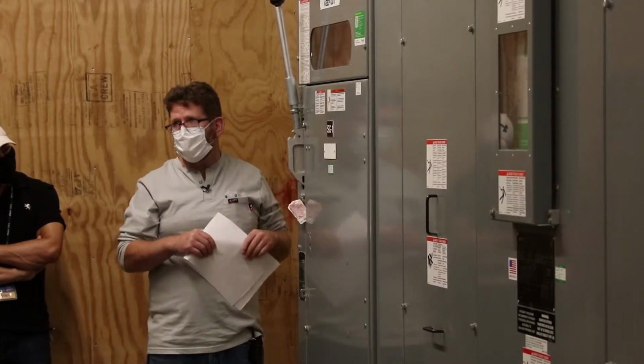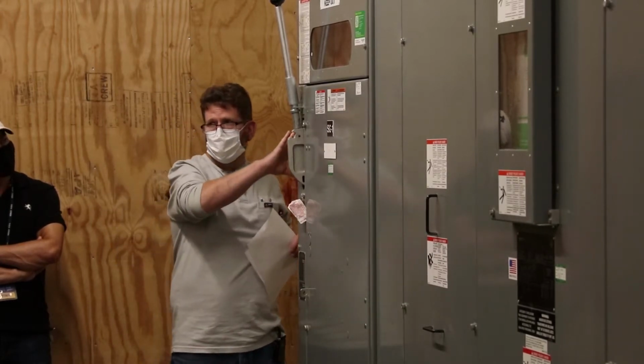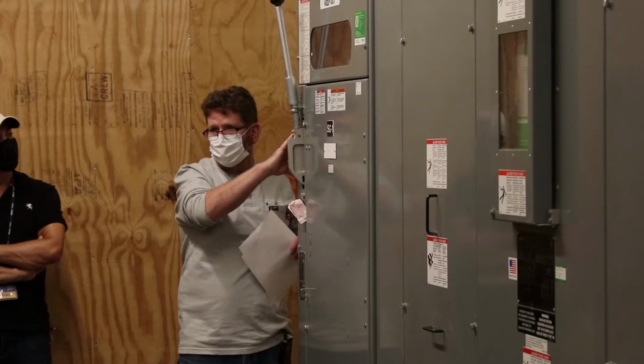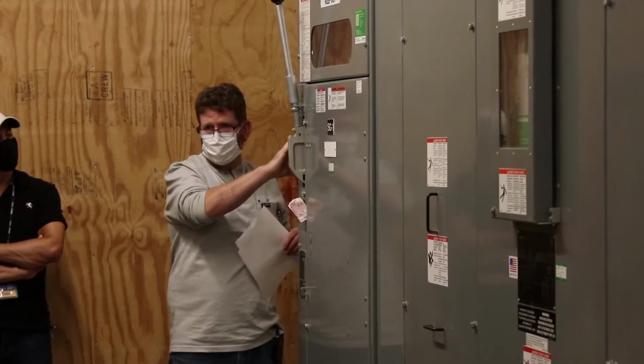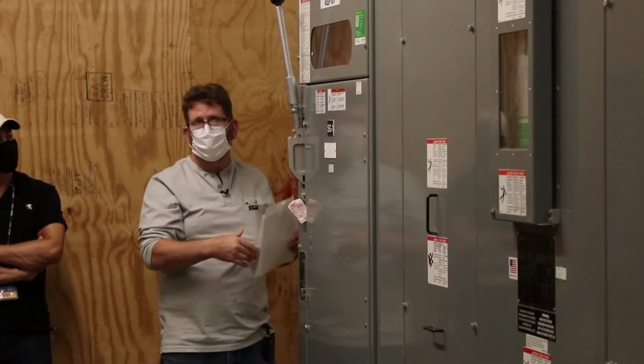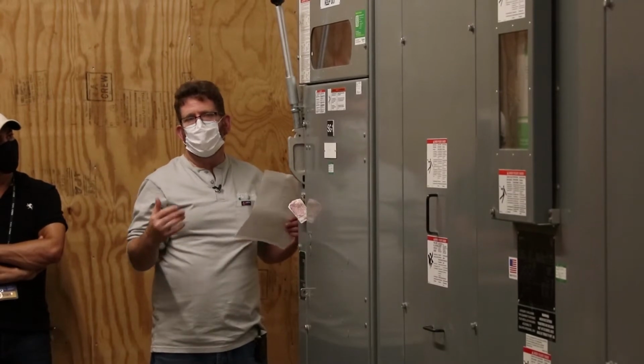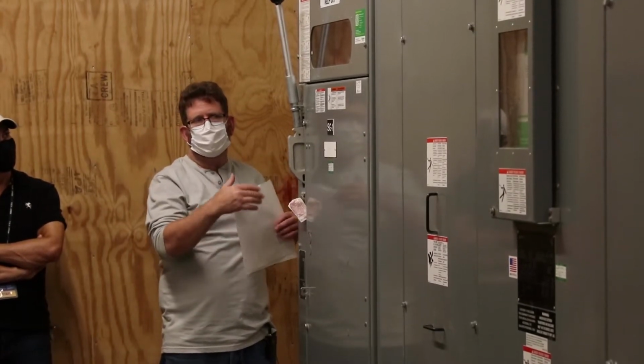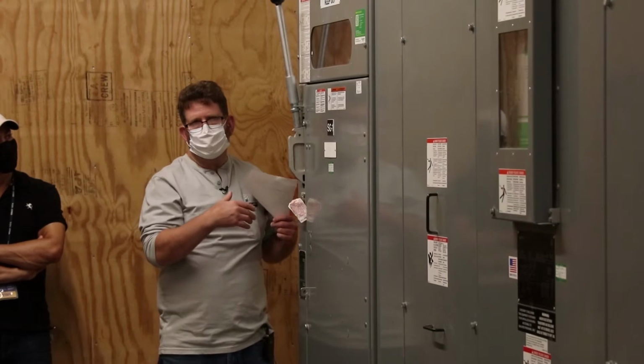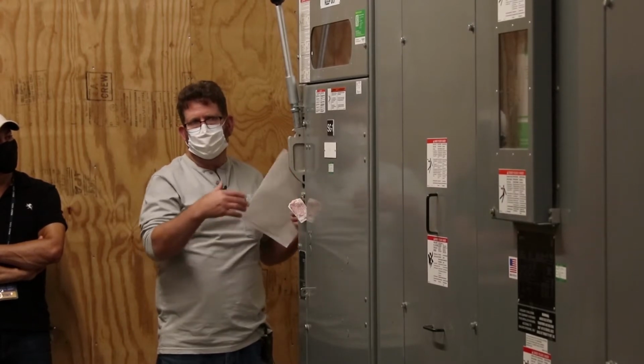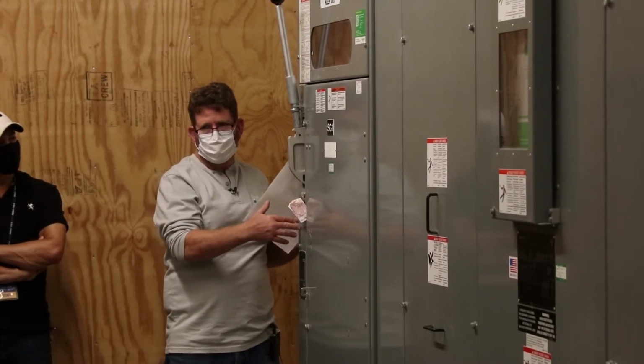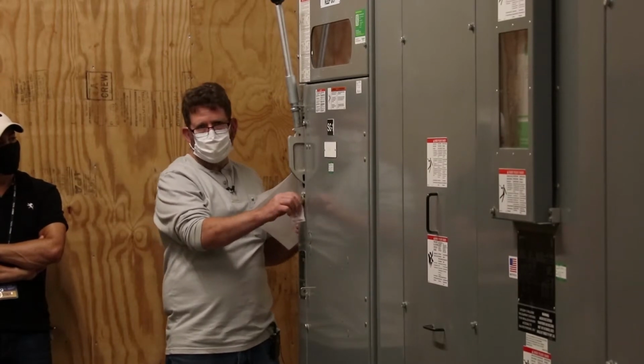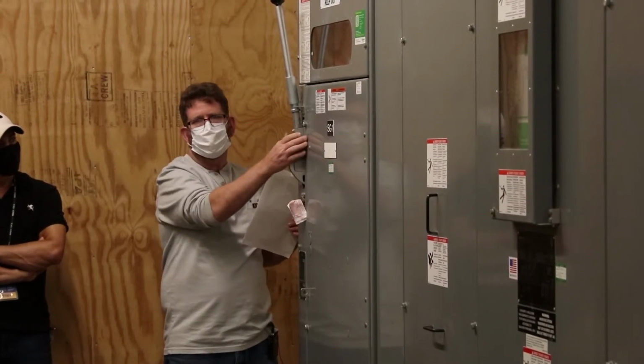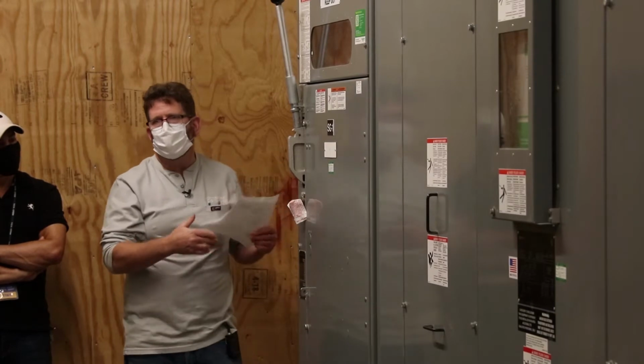The purpose of that is to minimize the load on this switch when operating. This is a load break switch, so it's rated to interrupt the load, but the number of rated operations between servicing is dramatically different if you're operating under load versus under no load. So the whole purpose of this key interlock is to prevent you from operating under load, to minimize wear on the switch.